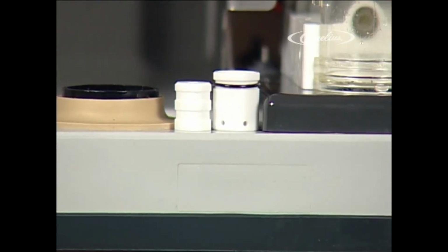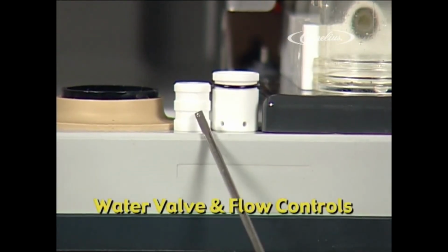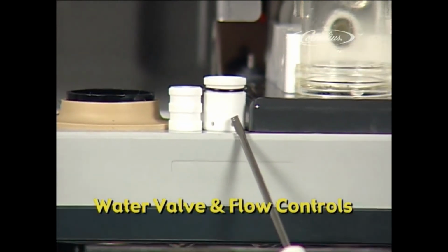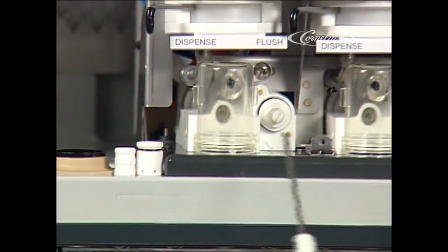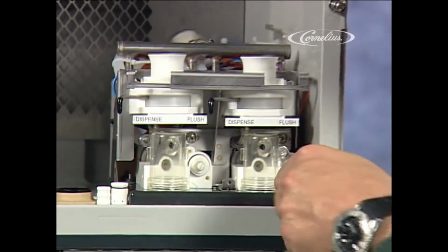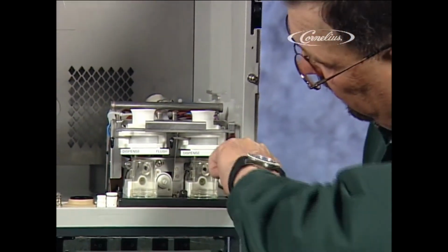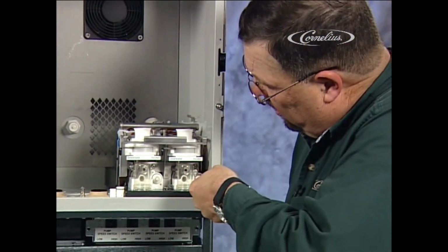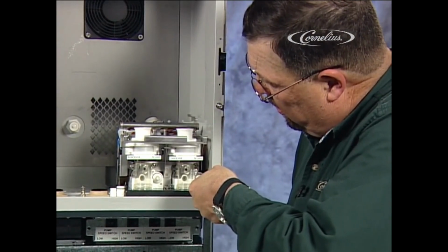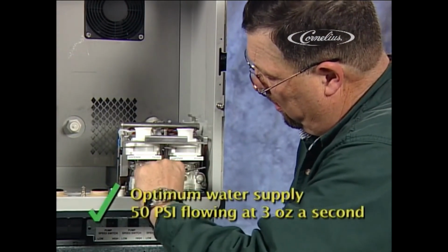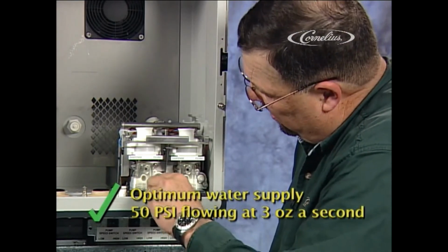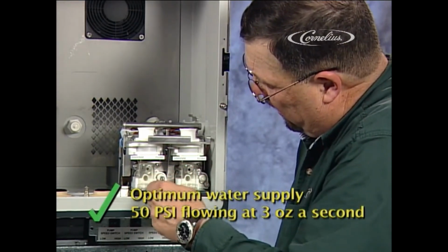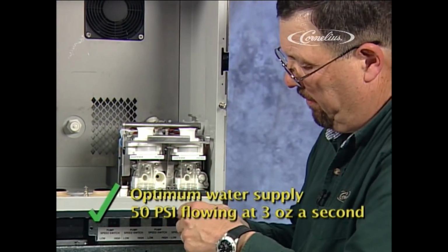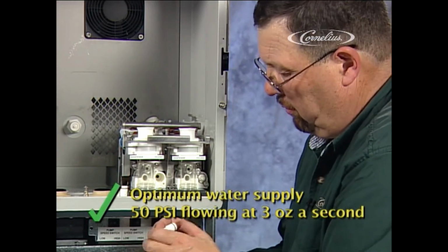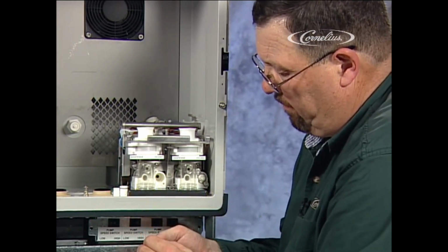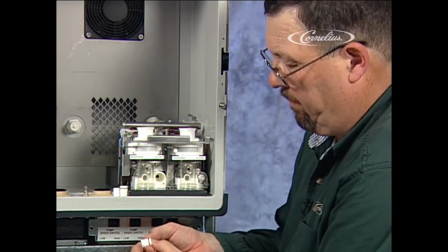The flow control is the ceramic spool and sleeve. It must move freely to regulate the water flow and thus maintain brix. It is turned clockwise to increase the water flow and counterclockwise to decrease the water flow. These are pressure compensating flow controls. They work best when the incoming pressure is regulated to 50 psi. Their effectiveness is significantly reduced if the water pressure is less than or greater than 50 psi. Again, the operating range is 20 psi to 80 psi.